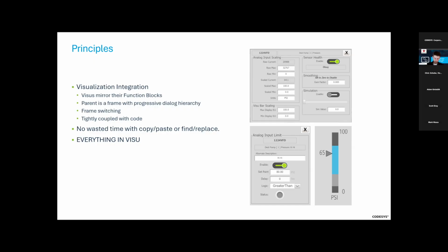One of the really cool things we found, specifically for our OEM customers, is that with CodeSys you can change your Ethernet settings for your Ethernet adapter within your application. You can change all the IP settings from the Visu in runtime without stopping the processor. Now, you have to blip the port, or at least the way we did it, you had to disable the port for one scan, but you can change your IP addresses and everything while running, and even change the protocols, which is very useful.